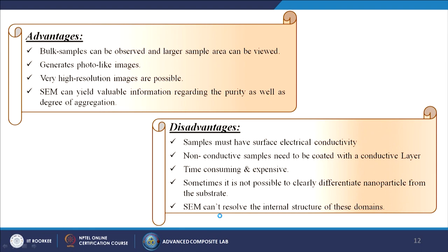Advantages of SEM: bulk samples can be observed, larger sample areas can be viewed, it generates photo-like images, very high resolution images are possible, and it can yield valuable information regarding purity and degree of aggregation. Disadvantages: samples must have surface electrical conductivity; non-conductive samples need to be coated with a conductive layer; it is time-consuming and expensive; sometimes it is not possible to clearly differentiate nanoparticles from the substrate; and SEM cannot resolve the internal structure of domains.